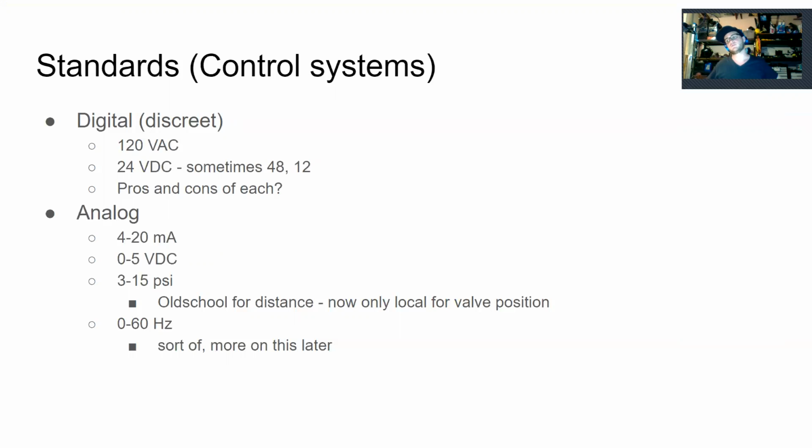Okay, so one of the advantages of AC is that you don't get voltage loss over distance. If you're just running short distance control signals, 24 volts DC is going to be fine. But if you're running in the hundreds of feet, you might actually get degradation in your voltage just from the resistance in the wire, to the point where when you energize that circuit and close it, I'm going to switch to the overhead again real quick.